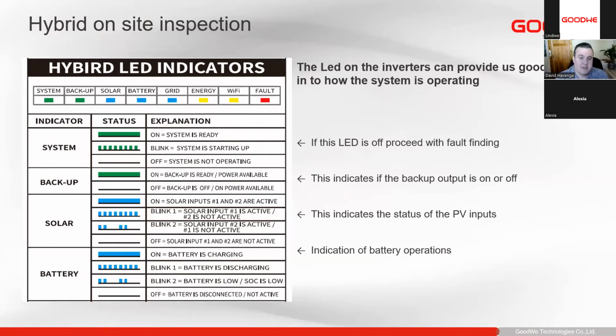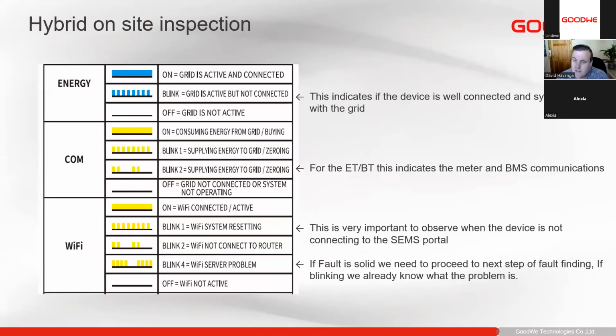I won't go into too much detail on these, but based on the fault that you're experiencing, there are different indicators that it could tell us. Especially Wi-Fi: if there is any problem with the Wi-Fi, one of the first things our service team might ask you is, what does the Wi-Fi LED indicate? Obviously, if there's a problem with the Wi-Fi, we cannot look from our side to see what the problem is. We'd have to have a look at the Wi-Fi indicator to give us a good idea of what the problem would be. But as I say, all of this is on the side of the inverter or in the user manual, which describes what each LED means, because each different model has different meanings for the LEDs.